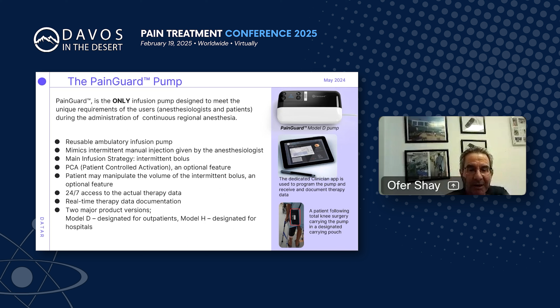It allows 24/7 access to the actual therapy data for the clinicians, and it provides real-time monitoring. We have two major products. Actually, one we have as a prototype, the other as the final product. It's what we call Model D, the design for outpatient. Model H, the design for hospital, will be launched later. And this pump is programmed via tablets, and there are some big advantages to programming any medical device using a relatively large screen rather than a very small and limited size screen. There are fewer errors.